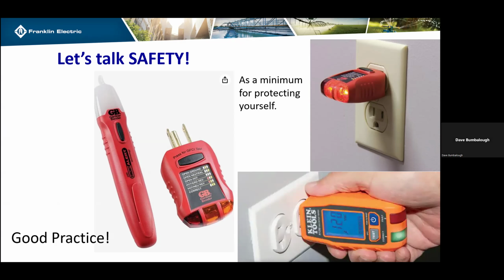Now, there are some advanced tools out there. I don't typically name drop, but as you can see, it does show Klein on there. They'll indicate what the voltage is. If you're dealing with a pumping system and you're venturing out to the well house or the building in which the controls are located, test some of the circuitry there. Just make sure that it is functioning correctly. That might be the issue altogether. Someone might have come in behind the electrician or the building contractor and added something and not fully understood how it was supposed to be hooked up. I've run into this situation before.